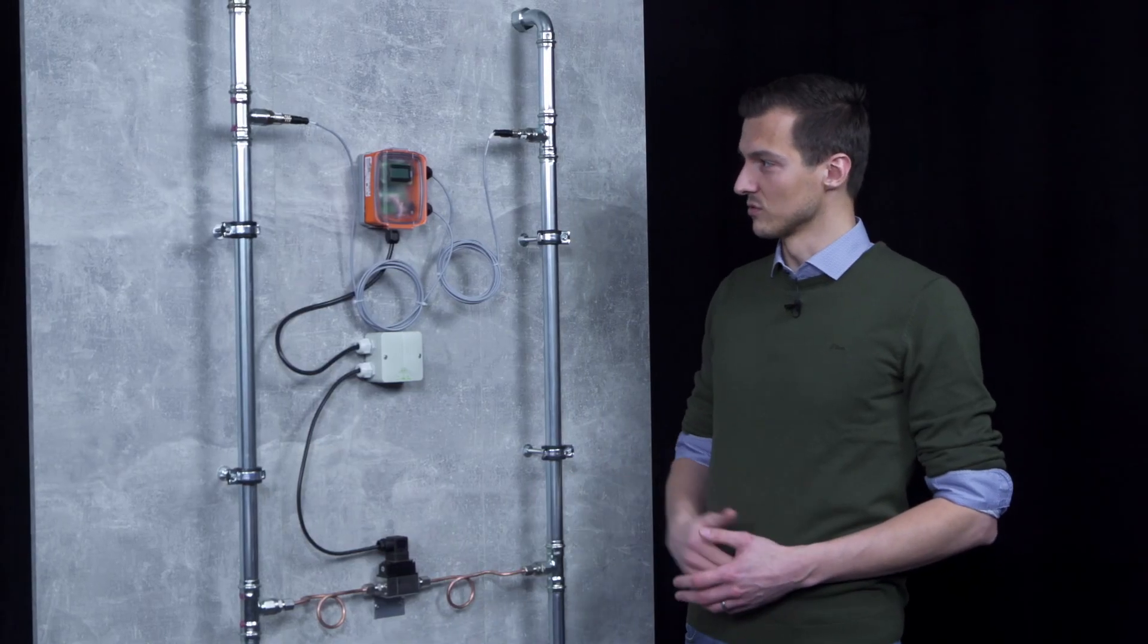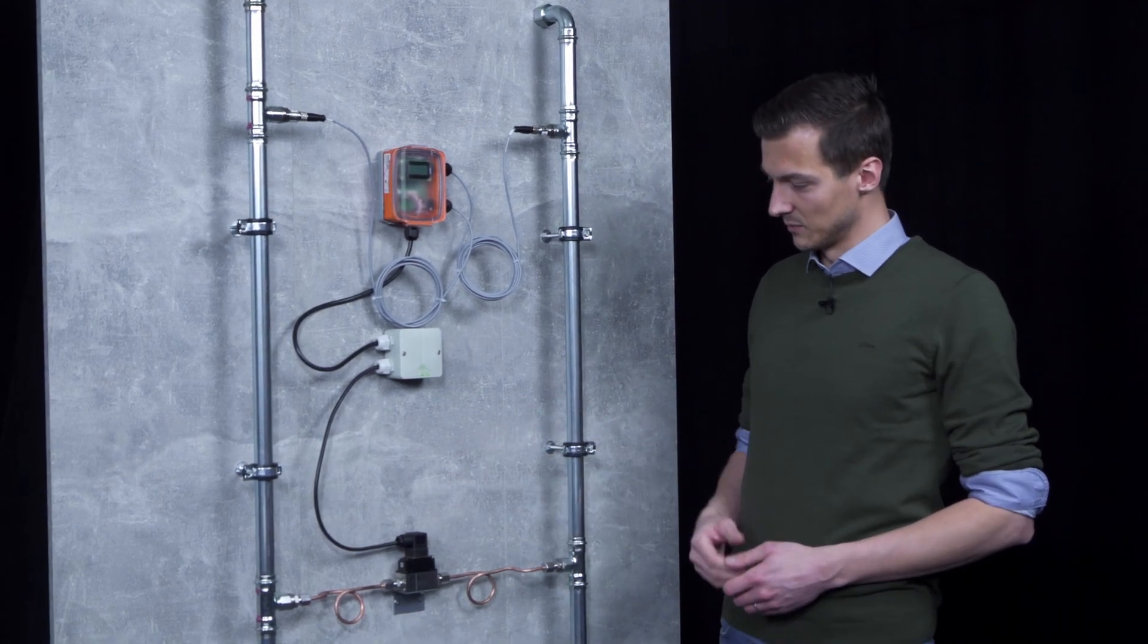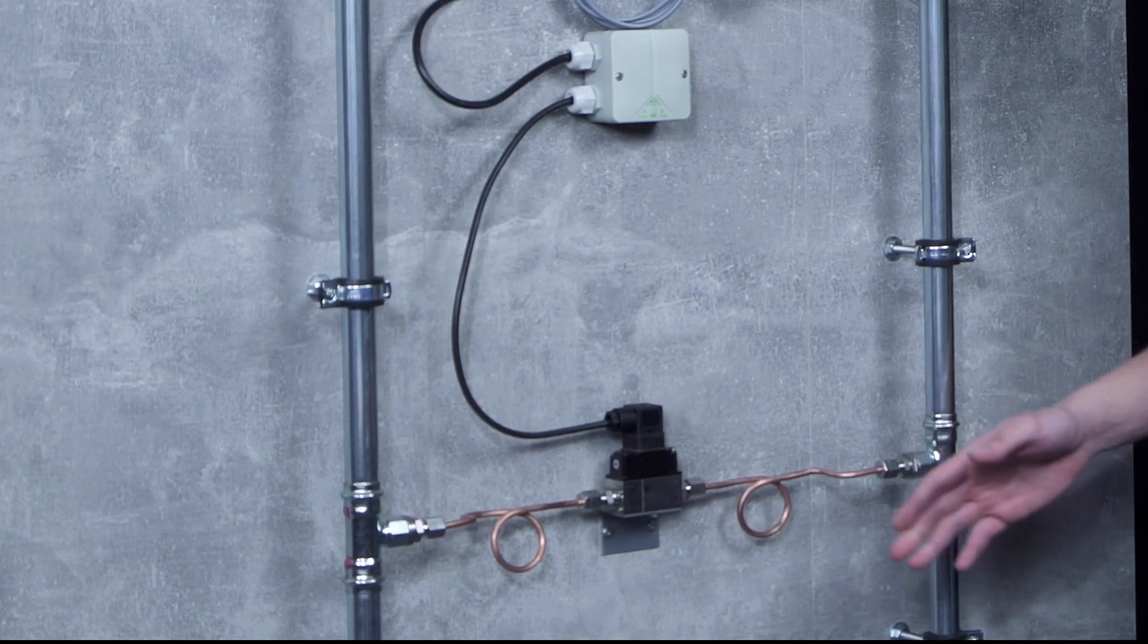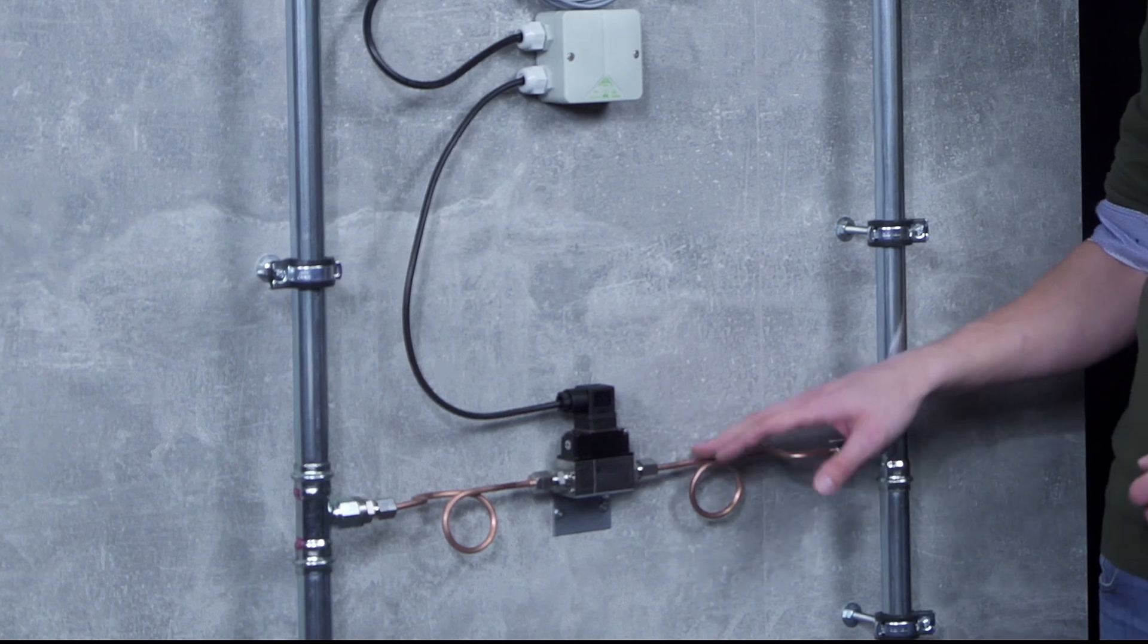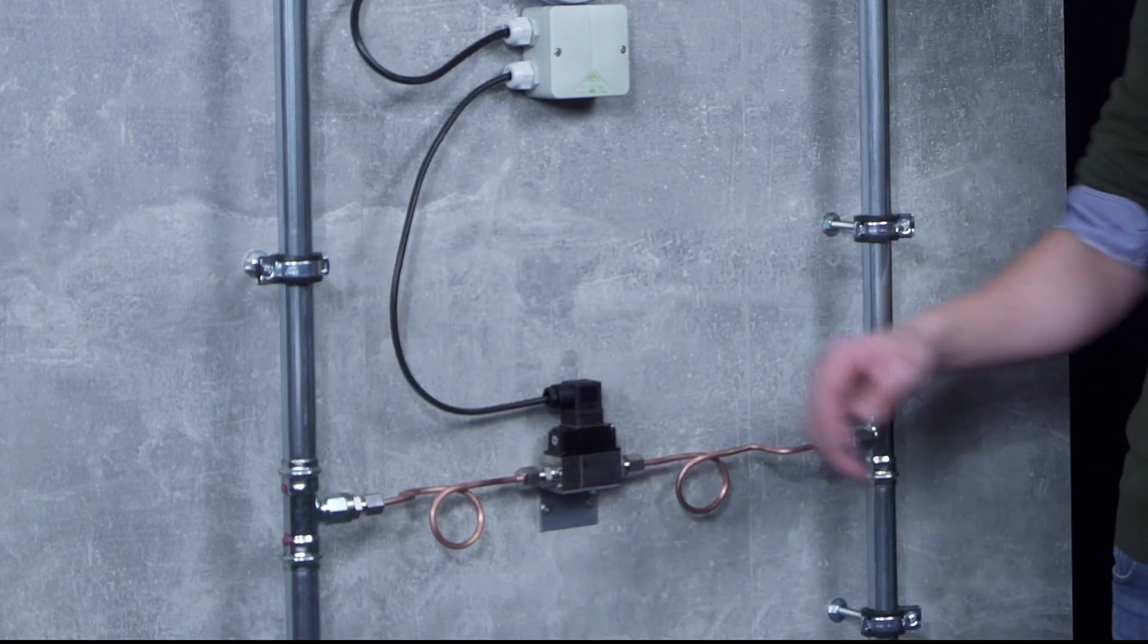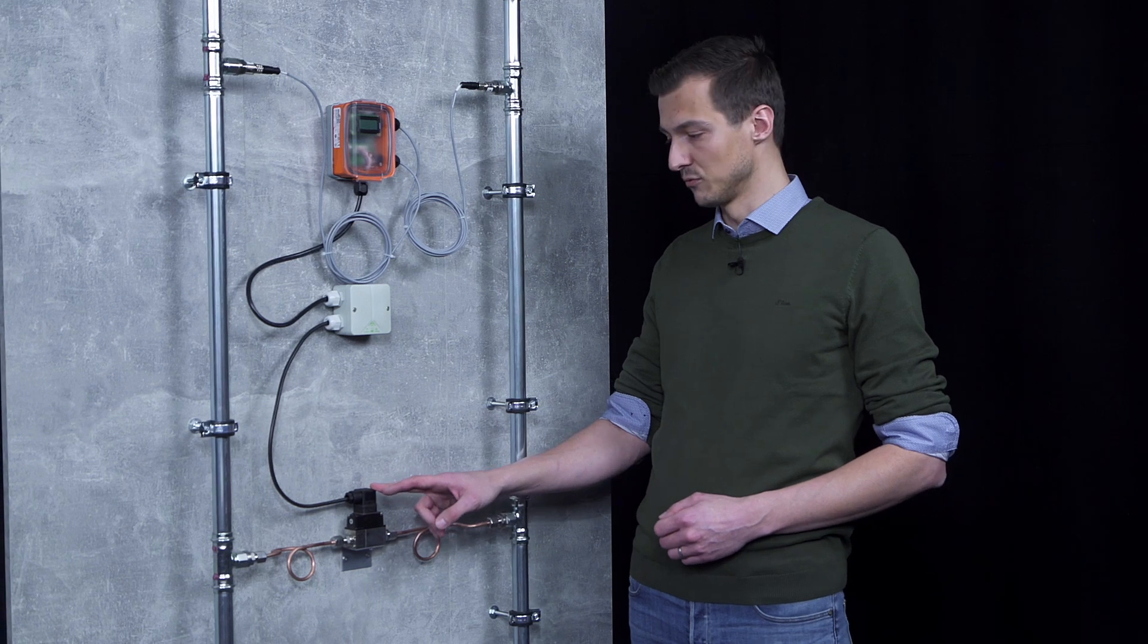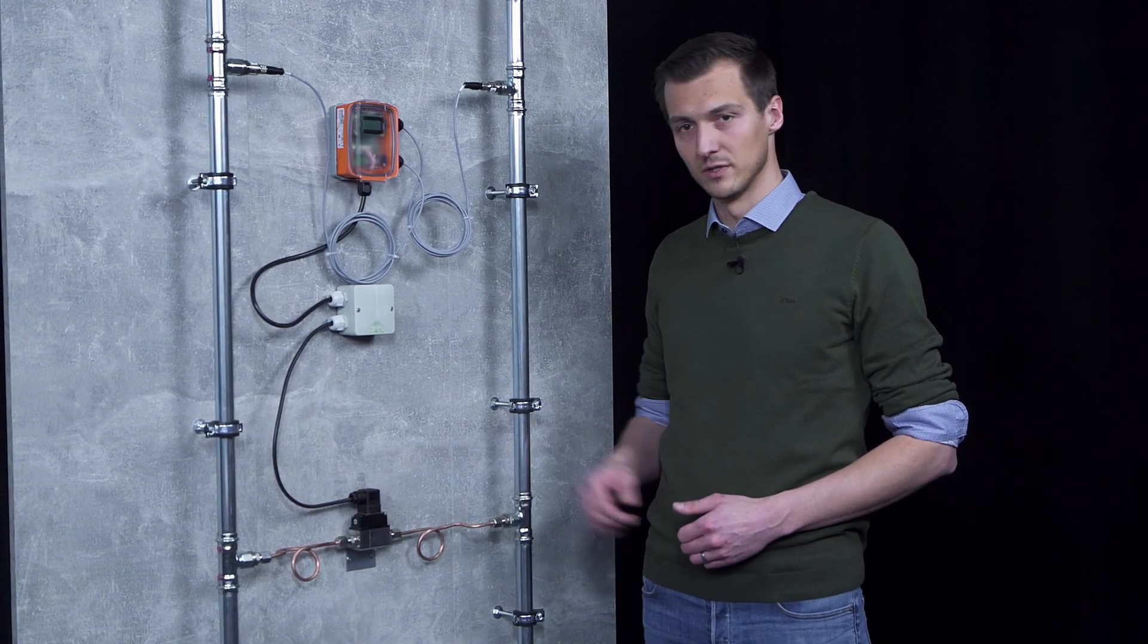We have now installed and commissioned both differential pressure sensors. Once again you see the 22 WDP, a solid, robust differential pressure sensor with a measuring diaphragm. This means it needs a hydronic connection to both strands. The WDP is available with different pressure ranges, as well as with voltage output 0 to 10 volts or with a 4 to 20 milliamp power output.